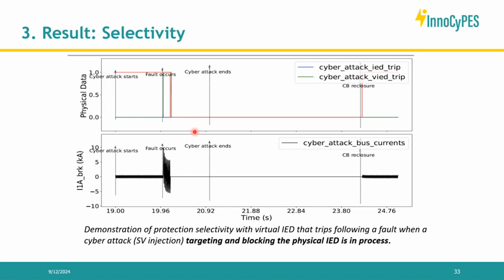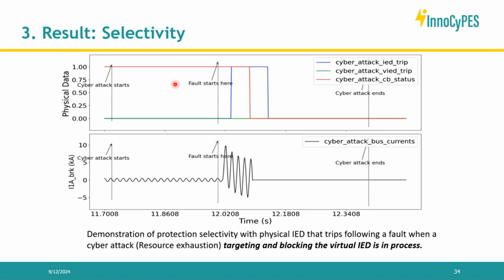Here it's the resource exhaustion. So here it's only the physical IED that will trip and clear the fault. We don't see the reclosure, but the fault will be cleared and the current passes to 0. Whereas the virtual IED never trips in this example. So it's the third pattern where the virtual IED never trips. Here it's just to demonstrate that when an attack that blocks the virtual IED occurs, the system will still trip, but only due to the selectivity from the physical IED.